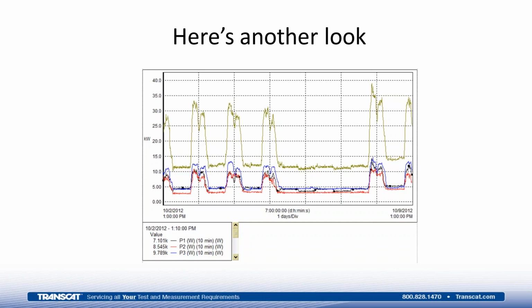So there is a benefit in understanding what your total power factor is for your facility and what the power factor of individual loads are, if for no other reason than to understand what energy cost is associated with that power factor. Unity power factor is the ideal situation. The utility does not have to do anything extra to produce your energy. Anytime you move away from unity, the utility has to do more work to produce your energy for you, and the way they measure that is with power factor. There are a lot of locations where if you're below 0.95, you get a charge or a fee added on to every kilowatt you use.